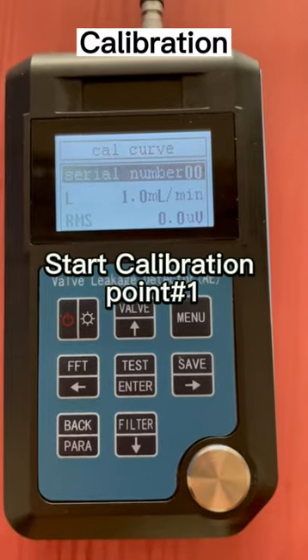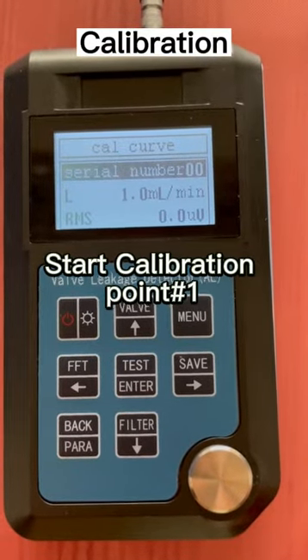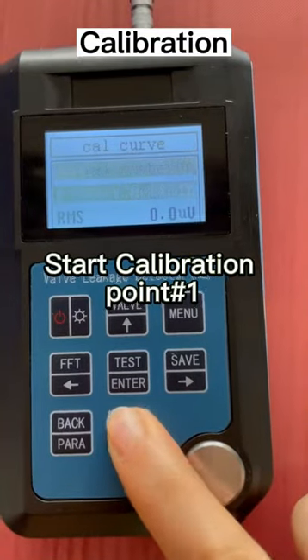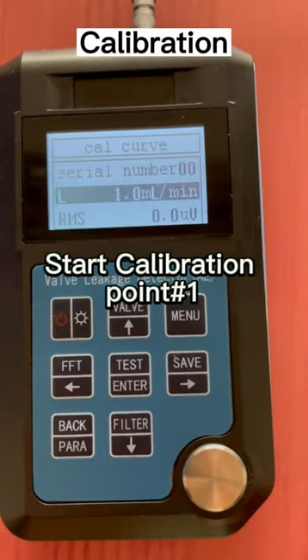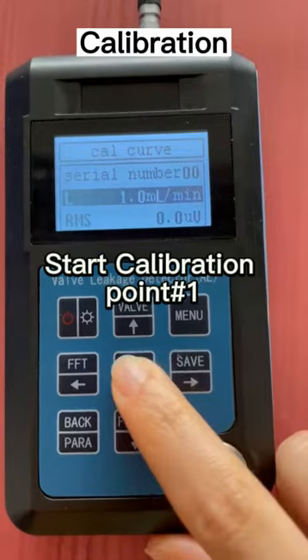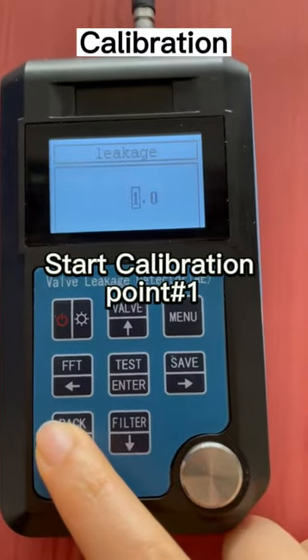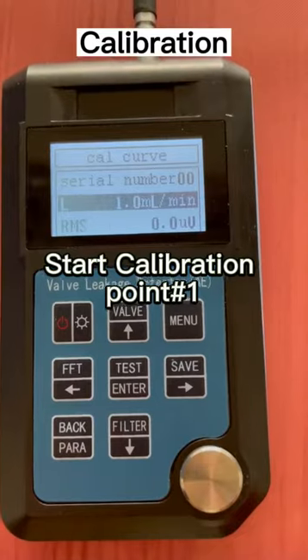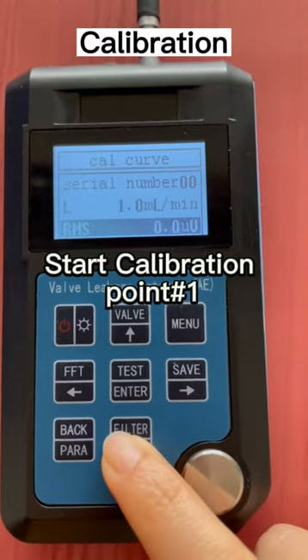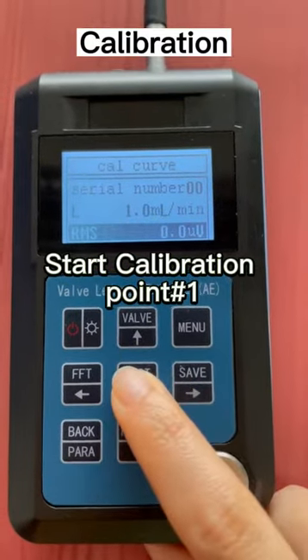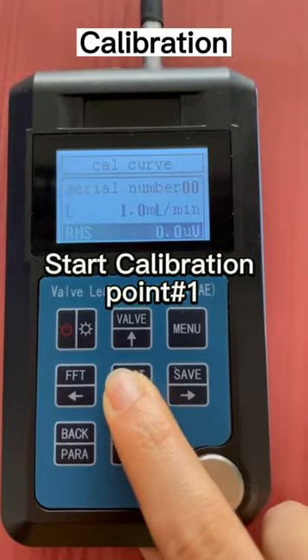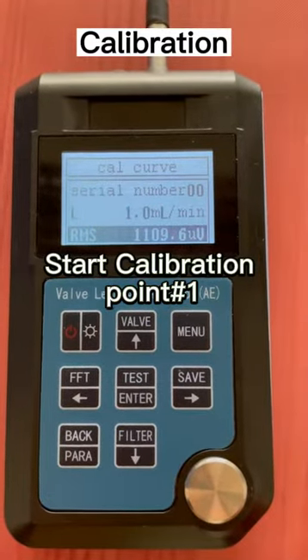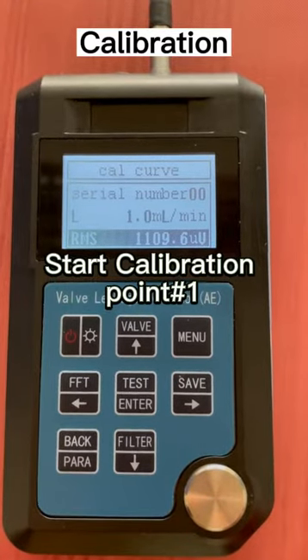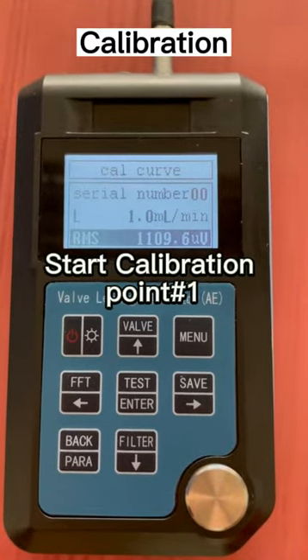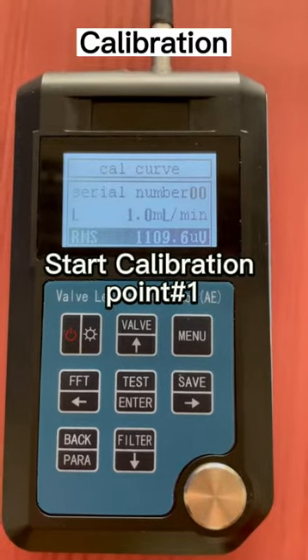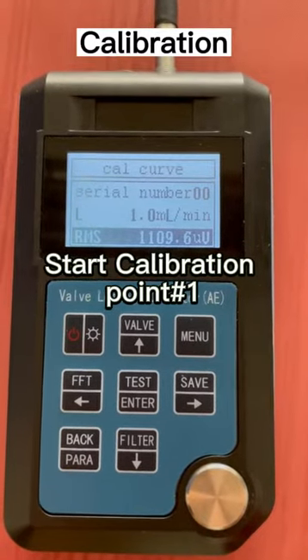Serial number is the current calibration point number. L means the reference leakage rate. Press the Enter key to modify the value and press the back key to exit the page. Move the cursor to RMS and press the Test key to start testing. It returns and stores the current RMS, ASL, and P values as the calibration point values at the reference leakage rate.